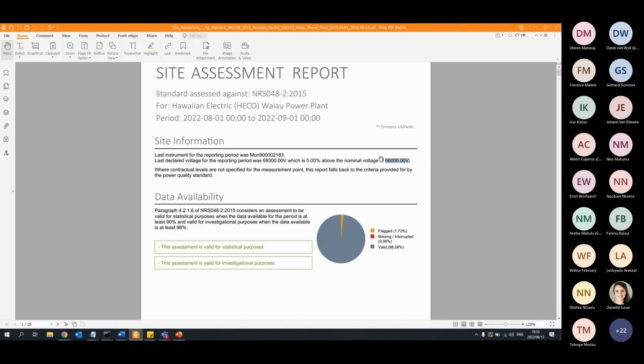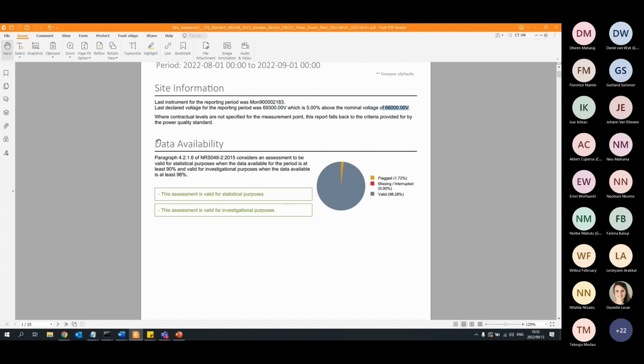So the voltage regulation and your percentages that are calculated will all be as a percentage of this declared voltage, 69,300, and not 66,000. All right, so firstly, we have a section where we look at the data availability. It's important to have a high data availability. This will just make your data more valid, to make your assessment more valid. If you have a lot of missing information, there could be periods where you missed an incident or a specific issue. So flag data is just the percentage of data that are flagged, normally due to dips or swells. So if there was a 10-minute sample, and in that 10 minutes there was, for example, a dip, then that sample is removed from the assessment to not affect your power quality assessment.